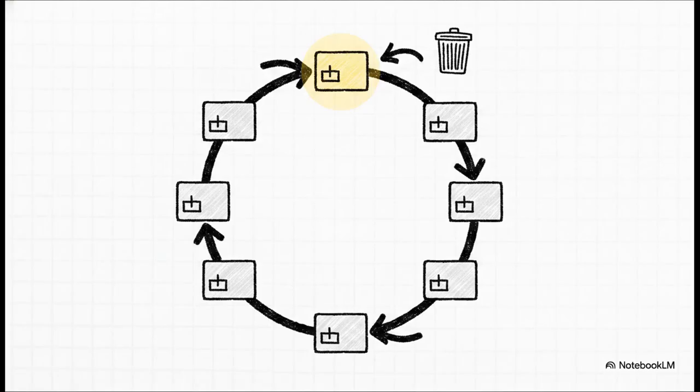From a technical standpoint, HSR applies the parallel operation principles of PRP, but onto a single ring topology. The sender node sends two frames, one out of each of its two ports. These frames circulate in opposite directions over the ring. Every intermediate node just forwards the frames it receives onto the next node. Crucially, when the originating node receives the very frame it originally sent out, it discards it to avoid creating an endless data loop.